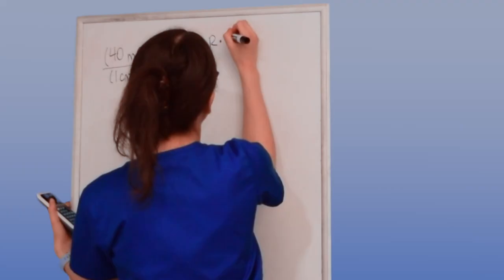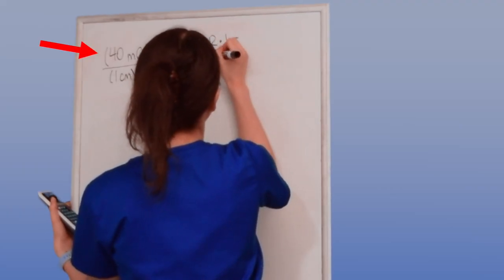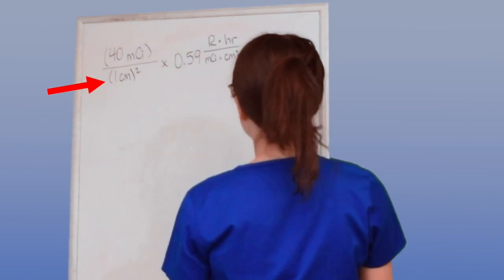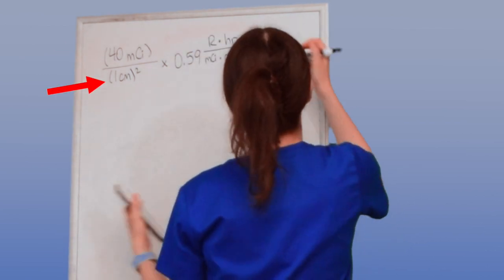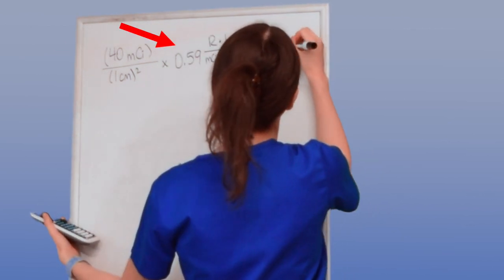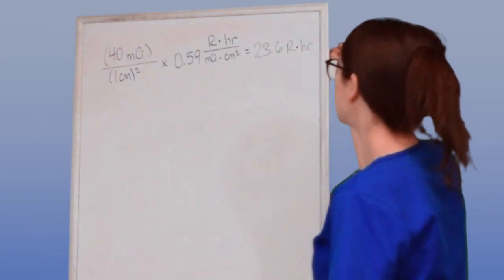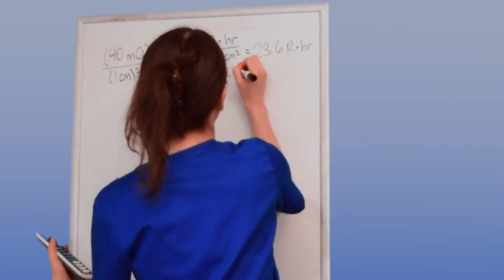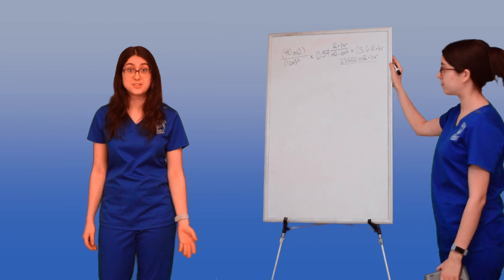My source is 40 millicuries, so that's my activity. If I'm grabbing it with my hand, my distance is pretty much none. We're going to use one centimeter, and then I'm just going to multiply that times my gamma constant. And what do I get? 23.6 roentgens per hour, 23,600 millirentgens per hour.